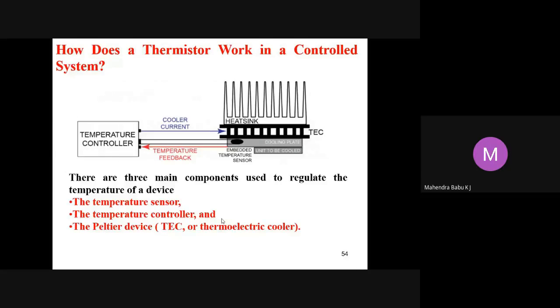This sensor head is attached to the cooling plate that needs to maintain a specific temperature to cool the device, and the wires are attached to the temperature controller. The temperature controller is also electronically connected to a Peltier device which heats and cools the target device. A heat sink is attached to the Peltier device to help with heat dissipation. The job of the temperature sensor is to send the temperature feedback to the temperature controller. The sensor has a small amount of current running through it called a bias current. The controller cannot read resistance, so it must convert the resistance changes to voltage changes by using a current source to apply a bias current across the thermistor to produce the control voltage.